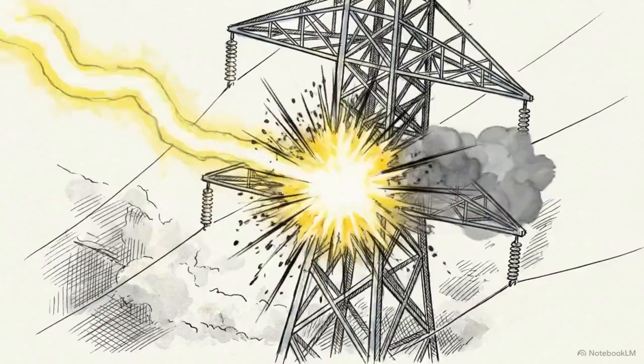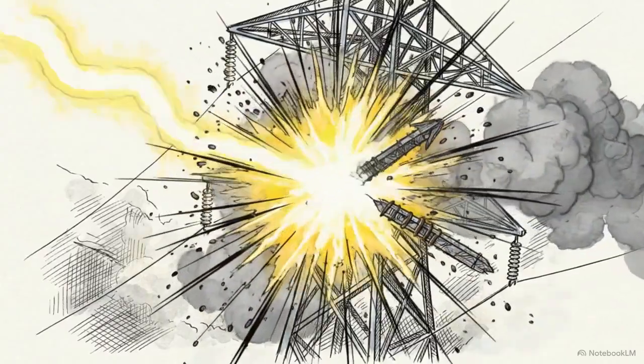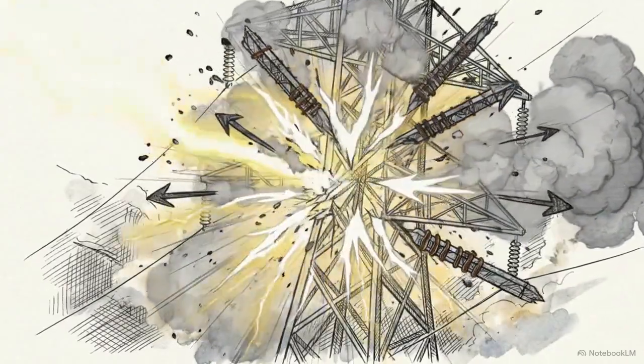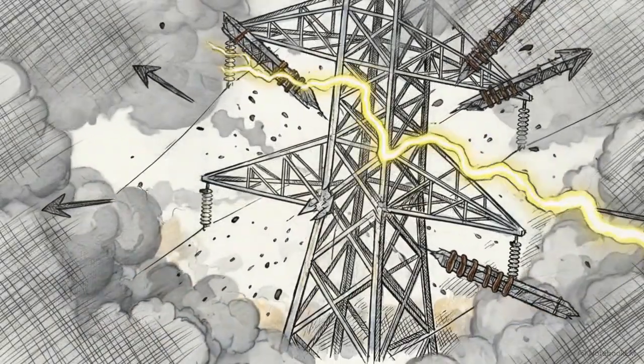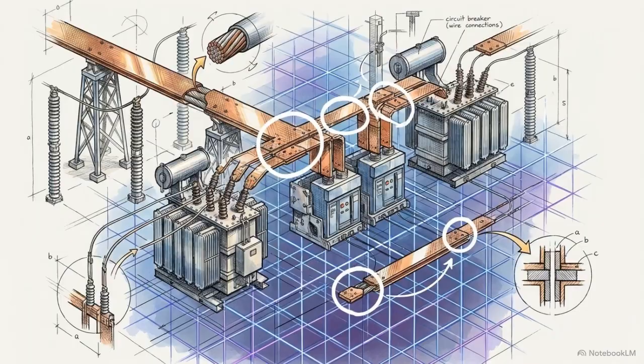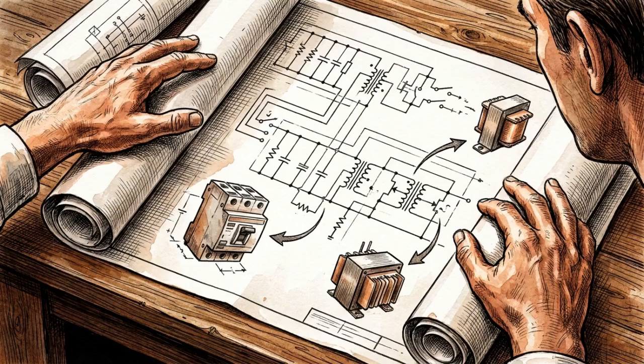These massive electrical faults are a statistical inevitability. Because the grid cannot rely on the impossible task of preventing every lightning strike or insulation breakdown, the physical architecture of the substation must be designed to survive them. To engineer that survival, grid operators use a rigorous topological language called the single-line diagram. This diagram uses a standardized alphabet of schematic symbols to map complex systems.